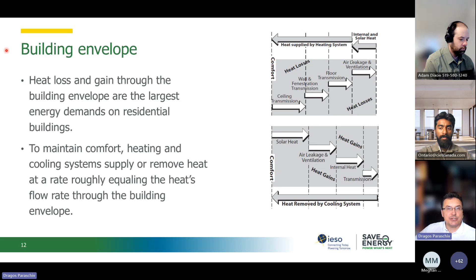What we see in this chart is the various heat loads, heat gains, and heat losses for our building envelopes that we need to be aware of, and which elements are more sensitive to heat loss or heat gain—transparent components, windows. Typically in any type of building, the best window is usually less performant than the worst opaque wall component you will see in your building. So we have to be aware of that.